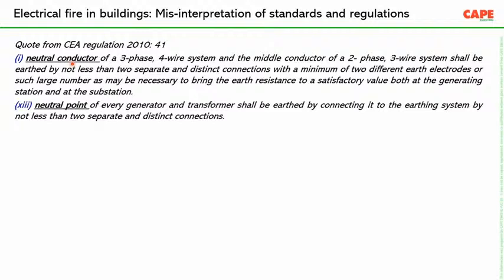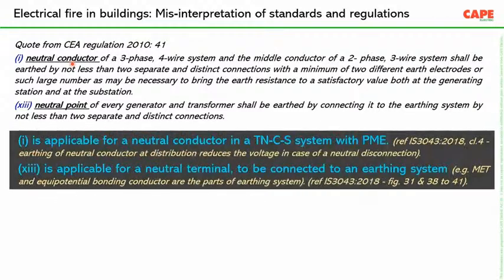Where is this applicable? Where do you run a normally long neutral conductor? A neutral conductor is running long for public distribution. So in a public distribution, the fourth wire, which is called the combined neutral and earth conductor, that conductor is earthed on the post, on the overhead line post. The neutral conductor is connected to earth pits, maybe 2 earth pits at maybe 3 places every kilometer or something like that. This is the meaning of the particular regulation. This has nothing to do with the terminal of a transformer or a DG.